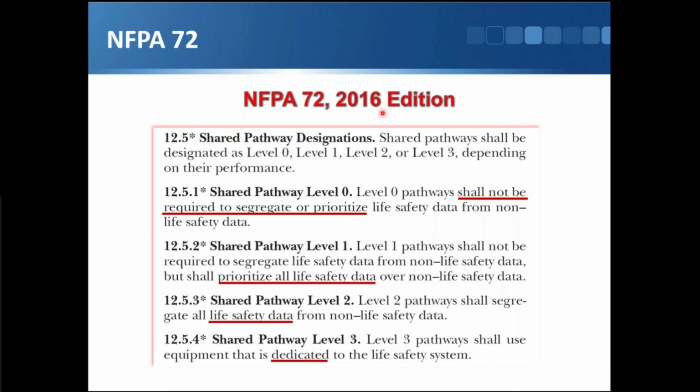what I think we have in there, at least it was discussed, and I think it is in the annex now, is that say you have a network switch and it's got some fire alarm stuff on it and some other stuff on it. You've designated certain sections for the fire alarm; within a managed router, you can define that a certain number of ports are dedicated to the fire alarm life safety system because you've prioritized them, you've done this work.